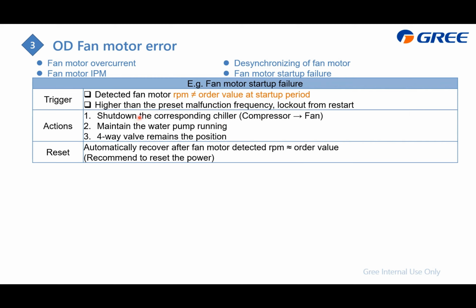And here is the action procedure, which is to shut down the corresponding chiller, first the compressor, then the fan, and also keep the water pump operating. And in heating mode, keep the four-way valve position. And of course it can automatically recover.